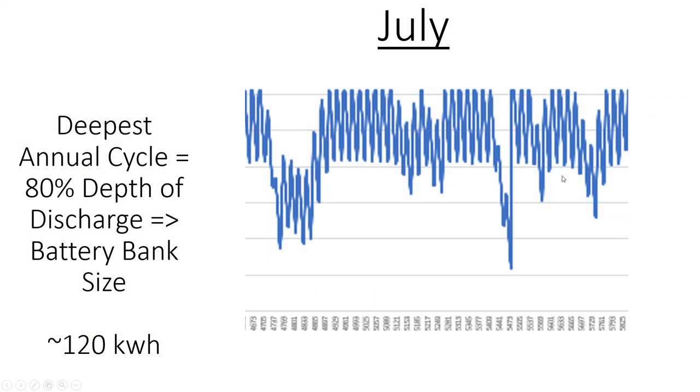And so, for instance, with our flooded lead acid batteries, they say, okay, well, we don't recommend cycling them more than 65%, but they're rated for a minimum of 80%, and so don't cycle them ever below 80%. But as far as regular operating, you can take them all the way down to 65%. And so we turn the generator on at 50% just to be on the safe side.